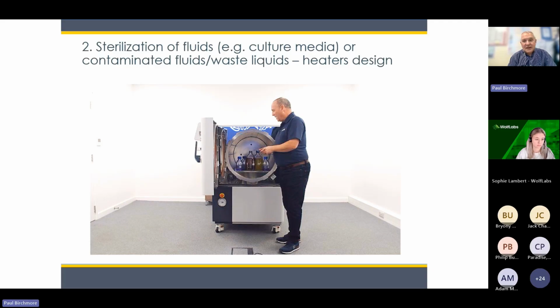So in order to prevent that, we counterbalance that, adding air pressure back in again. It's called air ballasting. So you prevent that massive reduction in pressure in the cooling phase, thereby preventing any overboiling of the media itself. So some of these features are interlinked. So you need to make sure that you have all of the features, as it were, to allow you to safely speed up the process.